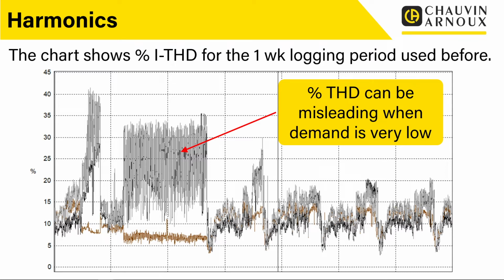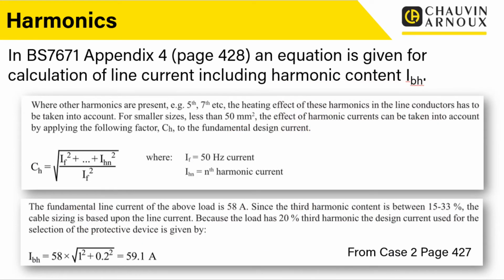So that has an impact really with things like cable sizing and other things within the installation, as we'll see now. So in BS7671 Appendix 4, an equation is given for the calculation of the line current, including harmonic content. You'll be familiar with IB, the design current, but we've actually got this one called IBH. So that's your design current, but corrected for the harmonic content.